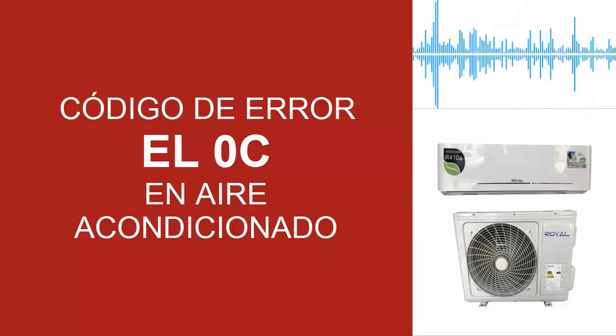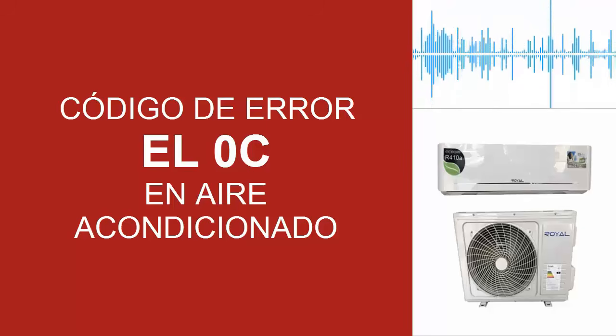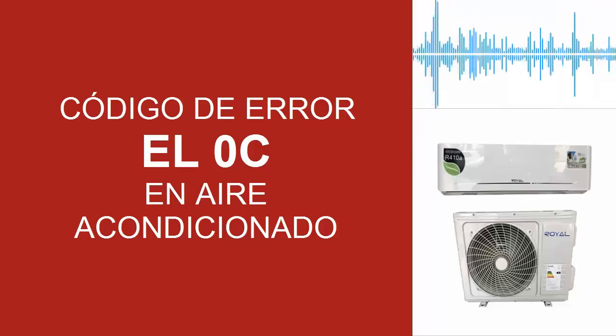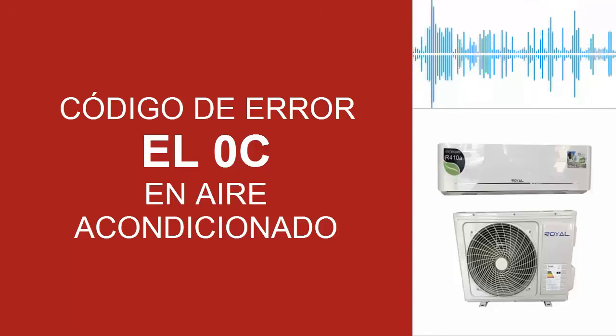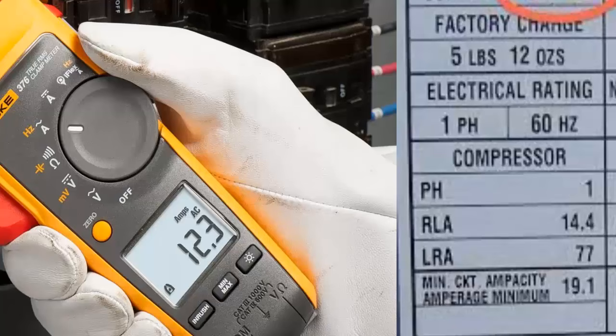It's essential to understand that the generation of the EL0C code depends on the tracking strategy that the equipment model employs. Confirming the actual presence of a leak is important. For example, when the equipment manages to turn on, you can use an amperage clamp meter to check the electrical current consumption of the unit.